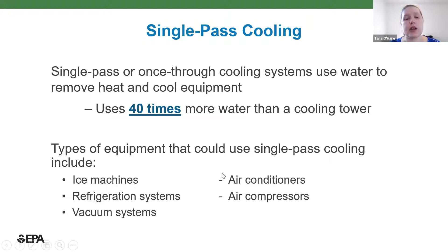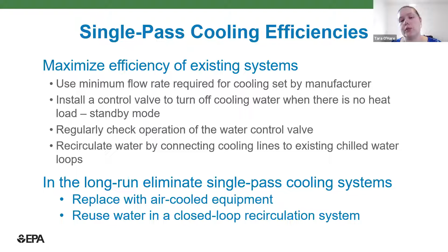Really, the name of the game here is to minimize the use of them. And if you can't get rid of them, we want you to maximize the efficiency of them while you have it. So use the minimum flow rate according to the manufacturer, and then make sure that you have control valves installed and that they are actually working. So you have to check them on a regular basis to make sure they're actually shutting the water off when you need it to. And then we encourage you to recirculate water when you can by connecting it to existing cooling lines or existing chilled water loops. In the long run, we encourage you to eliminate them completely by replacing them with air-cooled equipment and reusing the water in a closed-loop recirculation system.